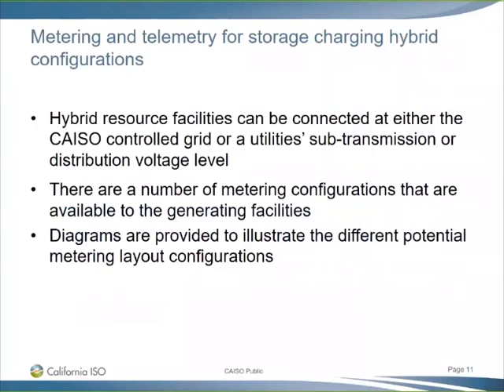This is Priyanka Namburi. I'm Lead Energy Data Acquisition Specialist at ISO, and we will be going over various scenarios and talking in detail about metering and telemetry for the hybrid configurations. The hybrid resources can be connected at the transmission level, at the ISO grid control level, or at the sub-transmission or distribution level. We have some diagrams in the next slides to talk about each configuration level and what the metering requirements are, depending on where the resource is connected to the ISO grid.